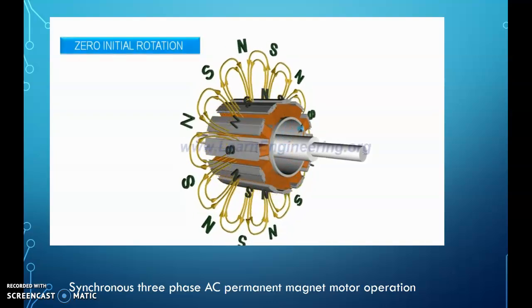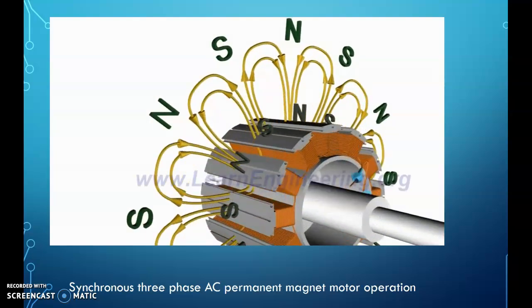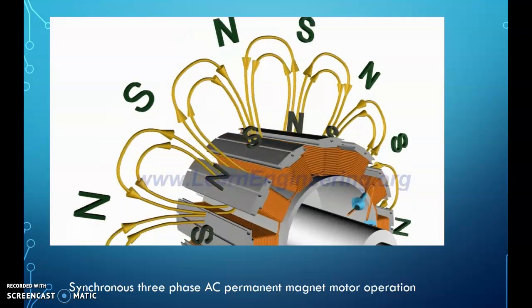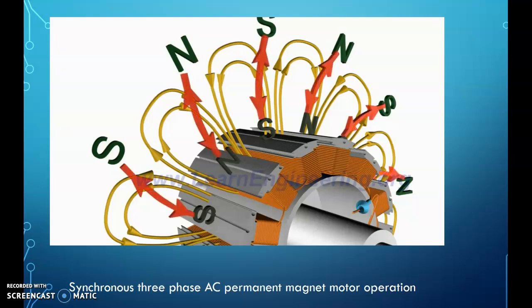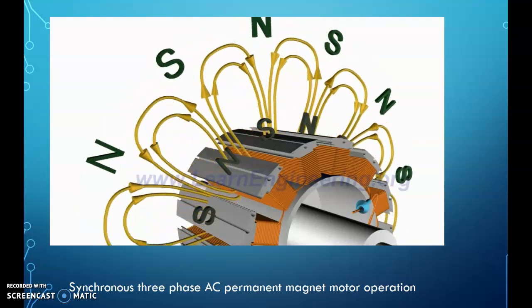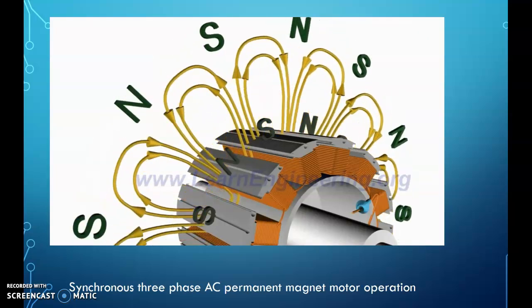But if the rotor has got no initial rotation, situation is quite different. North pole of the rotor will obviously get attracted by south pole of RMF, and will start to move in the same direction. But since the rotor has got some inertia, this starting speed will be very low. By this time, south pole of RMF will be replaced by a north pole, so it will give repulsive force. As a net effect, rotor won't be able to start, or synchronous motors are not inherently self-starting.